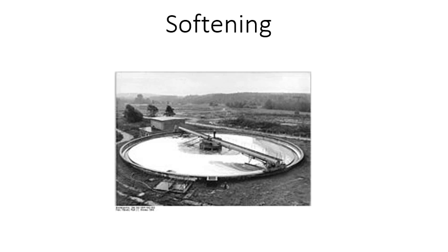Let's look at ion exchange softening. Hardness can be reduced to 0, but very soft water can be corrosive. The exchange of sodium for calcium and magnesium takes place on a resin charged with sodium chloride. Calcium and magnesium stay on the ion exchange resin, and the sodium ions will leave.